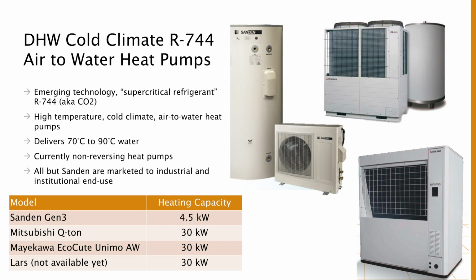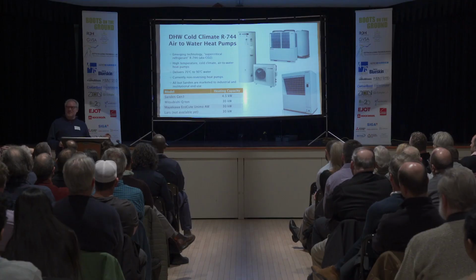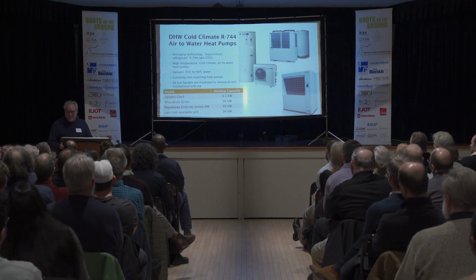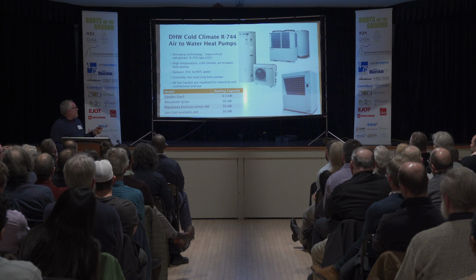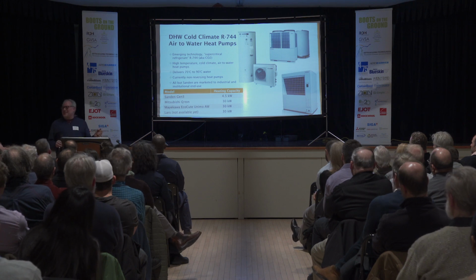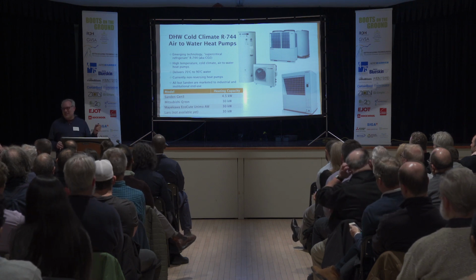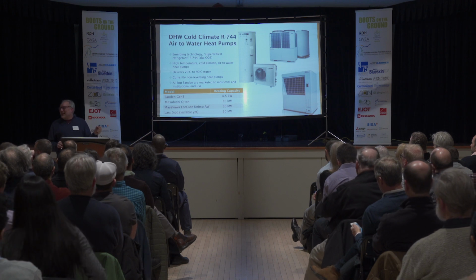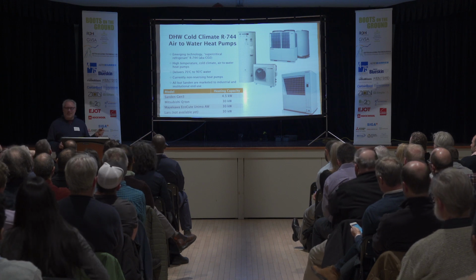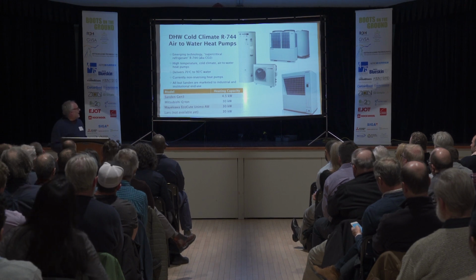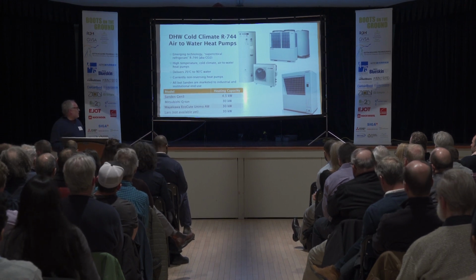This is Mitsubishi's. This is a new one I just found out the other day. These are all supercritical CO2 heat pumps. They produce 90 degrees Celsius water when it's minus 30 outside. They are at insane pressures on the inside. Your normal refrigerant guy is not going to work on this because they're running at about the same pressure as a diesel engine fuel injection system. That said, more and more of these seem to be showing up.